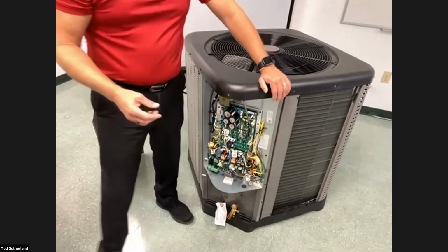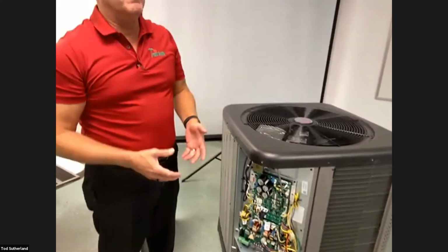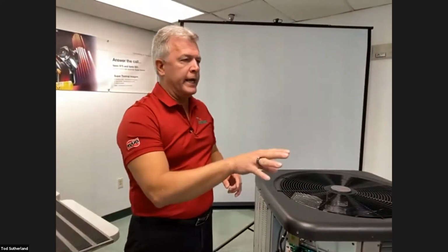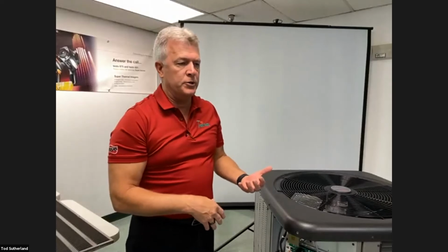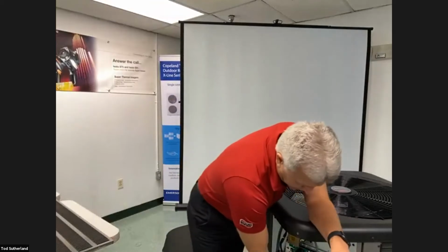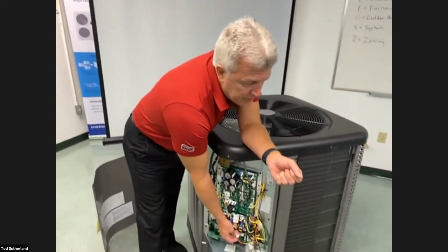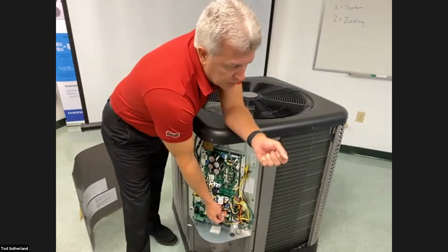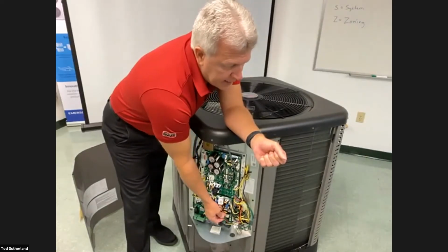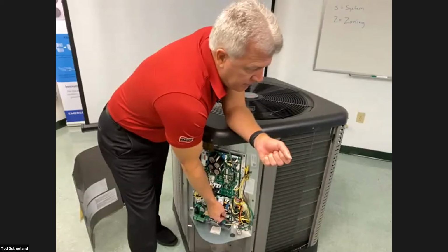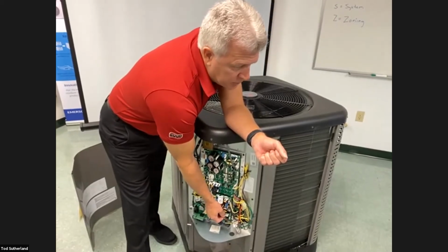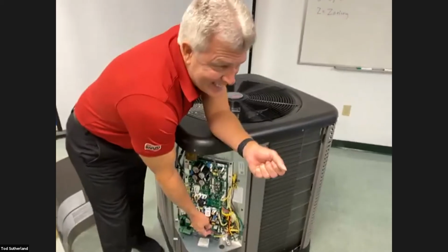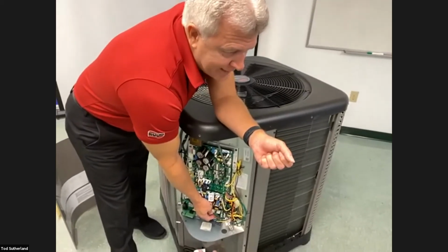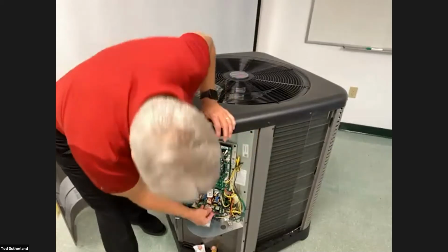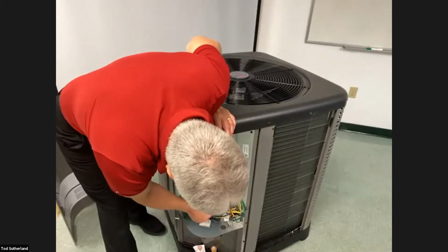When you're checking the voltage, we're going to go through that a little bit better when we get over to the air handler, because you can actually see the pressure transducer in the air handler. So we'll go into that in more depth, but the pressure transducer on the suction line is always going to be red, green, and black. On the liquid line, it's going to be red, purple, and black. Your red and black is always the voltage going from the board to the valve, and your green and black is your voltage coming back to the board. And that's DC voltage. That's volts DC. And we'll talk about measuring that and how to calculate whether or not that transducer is good or not.